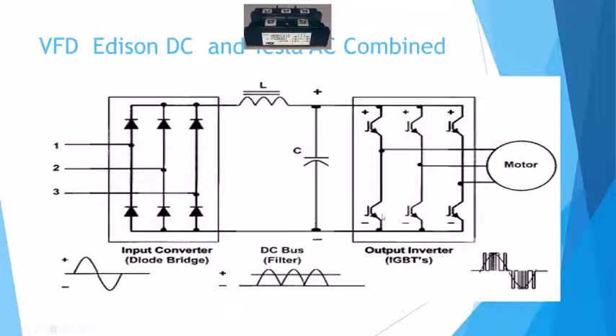So you can see this is an original diagram of what's happening. On a variable frequency drive, we're first converting that three-phase power to DC. So we're creating DC power in here. On a 480 volt circuit, this would be about 700 volts DC, 700 to 800 volts, depending on how much input voltage you got. So people understand a little bit.